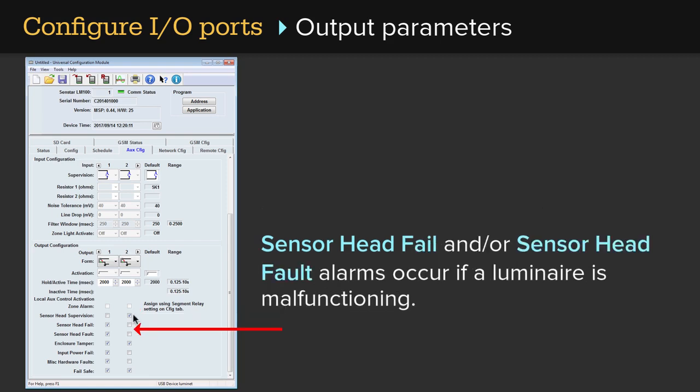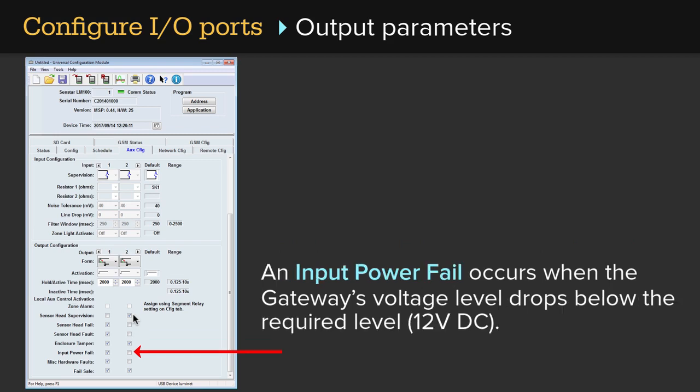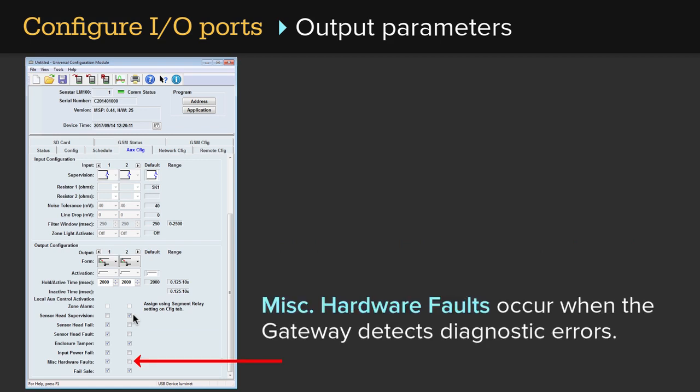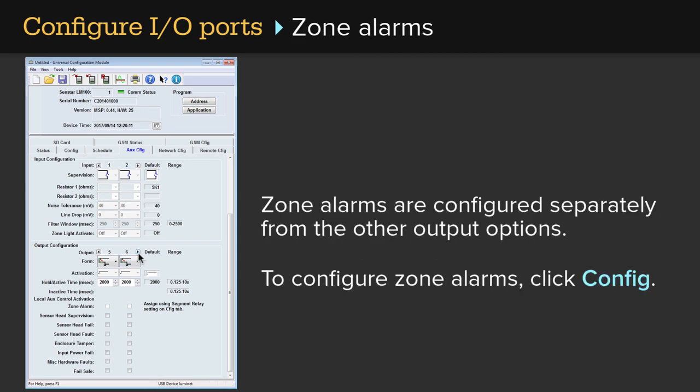Sensor head fail and/or sensor head fault alarms occur if a luminaire is malfunctioning. Enclosure tamper alarms occur when the gateway's door is opened. An input power fail occurs when the gateway's voltage level drops below the required 12 volts DC. Miscellaneous hardware faults occur when the gateway detects diagnostic errors. Fail-safe alarms occur when the gateway is generating critical hardware errors or a power failure is about to occur.